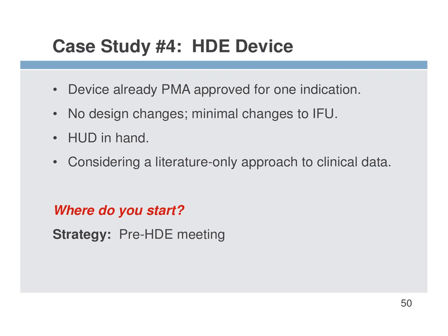I think that may in fact be your first question in your pre-sub. You may say, we want to go for this indication. If we do, here's the kind of testing we think is necessary. If we're also considering this indication, do we think this testing is necessary? And that might generate enough of a meeting to be done with it.